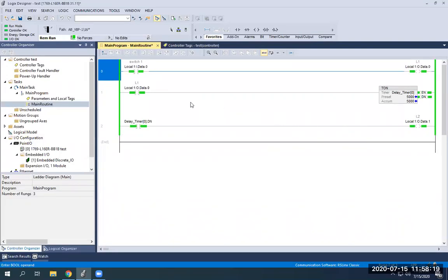So in a program, that's exactly what would happen. You can use a timer on delay to create a delay to get another output. That way they don't come on at the same time. Practical applications, this might be something where you want one motor to start up and get a good pressure build before another motor kicks on and keeps an assembly line or a fan going. But this is just a practical example of how to create a digital timer on delay and what it can be used for.